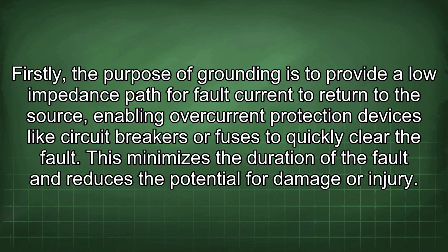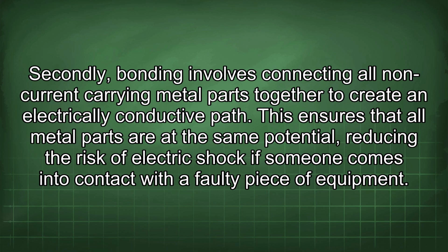Firstly, the purpose of grounding is to provide a low impedance path for fault current to return to the source, enabling overcurrent protection devices like circuit breakers or fuses to quickly clear the fault. This minimizes the duration of the fault and reduces the potential for damage or injury. Secondly, bonding involves connecting all non-current carrying metal parts together to create an electrically conductive path. This ensures that all metal parts are at the same potential, reducing the risk of electric shock if someone comes into contact with a faulty piece of equipment.